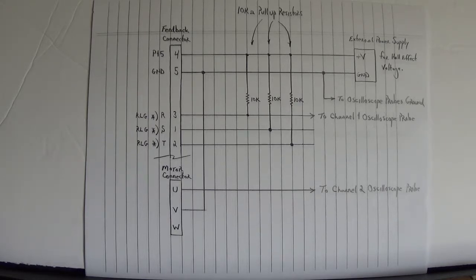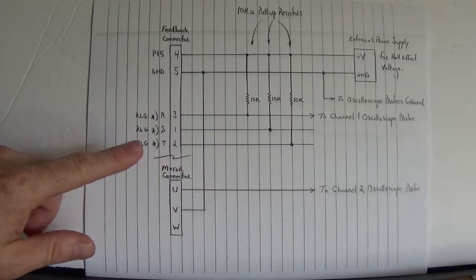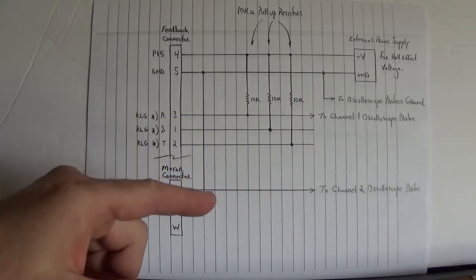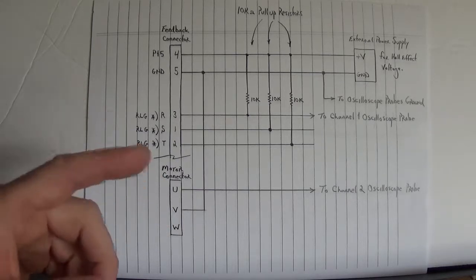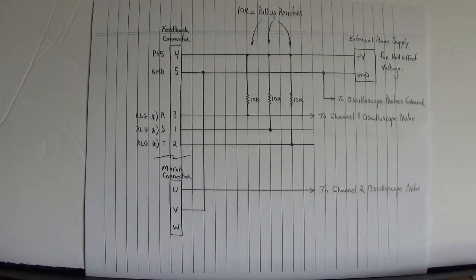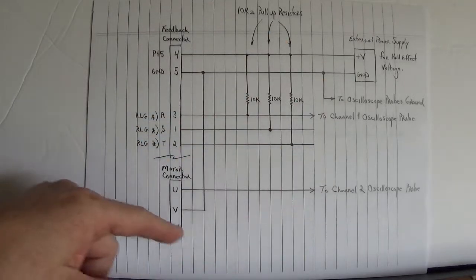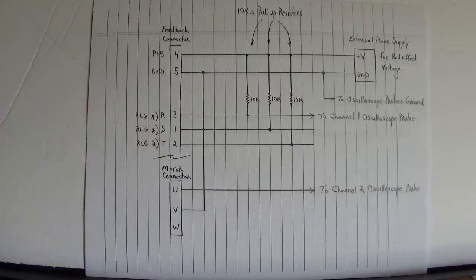Make sure that you don't have that CRT oscilloscope connected back to earth. And when you isolate that scope from earth ground, don't touch any metal on that oscilloscope, because that high voltage we're seeing right here will find its way back to earth through you. When you isolate your scope off of earth ground, don't touch any metal.